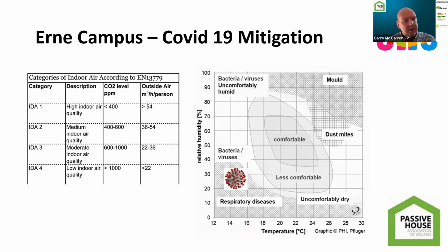Looking at the chart, there are different categories, 1, 2, 3, and 4, of indoor air classification, calculated by CO2 levels in parts per million. For category 1, you have to be less than 400 CO2 parts per million. Category 2 is between 400 and 600, which is really good. Category 3 is 600 to 1,000. Anything above 1,000 parts per million is considered low indoor air quality. You'll also see the amount of supply air needed to stay within those thresholds. Passive house sizes the supply air at roughly 30 cubes per person per hour, which means you come in between 600 and 1,000 CO2 parts per million.